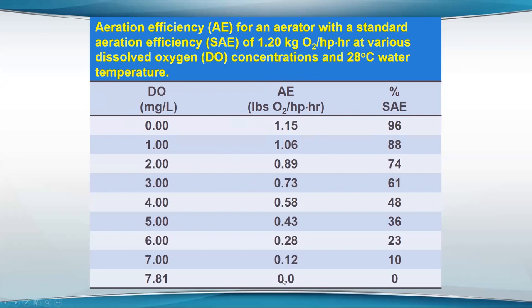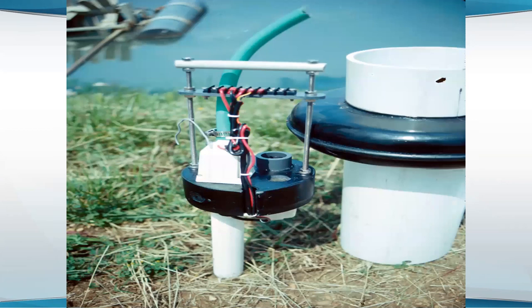If the water has more oxygen than saturation, the aerator actually becomes a deoxygenator, increasing the rate at which oxygen escapes to the air. They now make devices you can put in the water to monitor oxygen concentration and send a signal to start and stop the aerator. You program in what oxygen concentration you want the aerator to come on and go off, and manage the aerator through this automatic monitoring system to prevent both over-aeration and wasting energy.